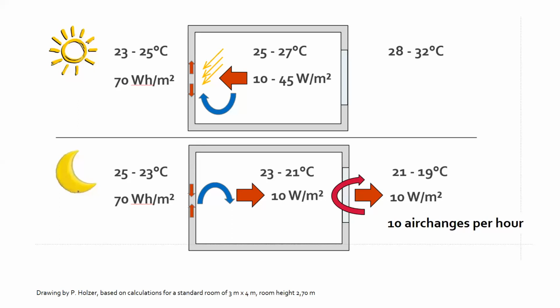If we allow our room to be at 27, thermal mass will do its job as long as the wall temperature is significantly, let's say, 2 Kelvin lower. Then it will take up heat, and I calculated it against the treated floor area of a characteristic room of something like 3 times 4 meters. These are characteristic exemplary values relative to the treated floor area. So the walls could take up 70 watt hours during a day, and to make them release this heat during the night, we have to be sure that it's again 2 degrees lower in the room during the night.